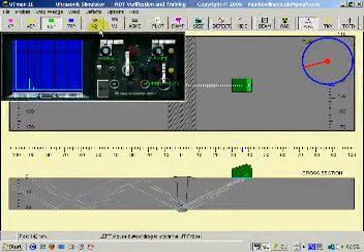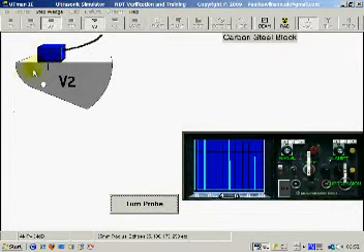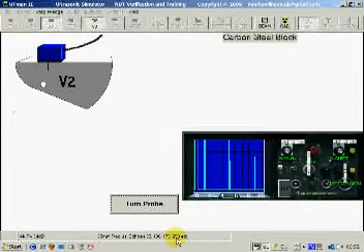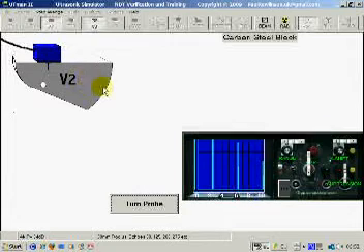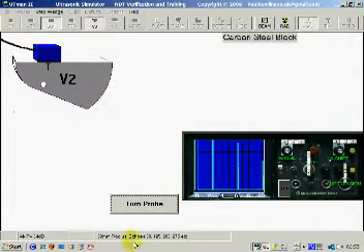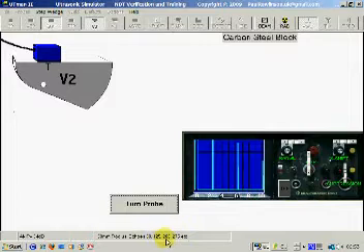The other method is on the V2 block, which has a radius of 25 and 50. Here we will get multiple echoes of 25, 100 millimeters, 175 and 250.